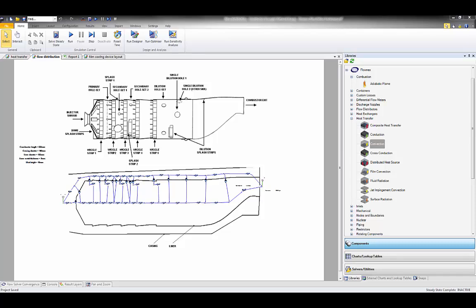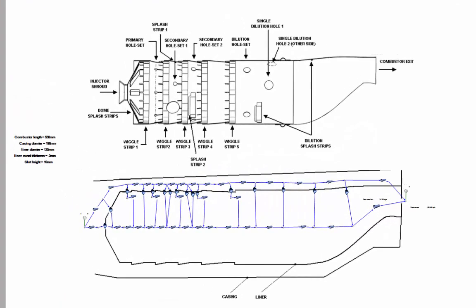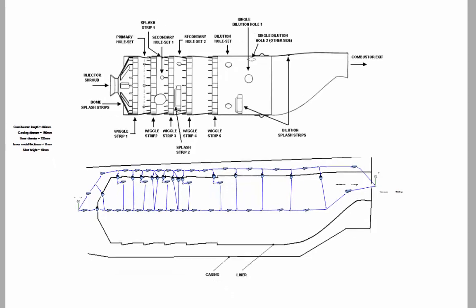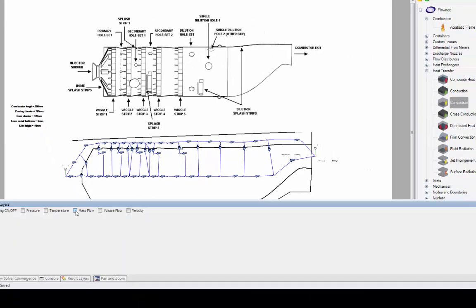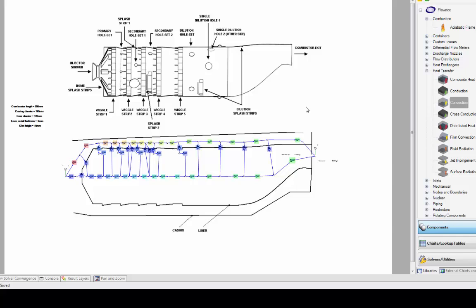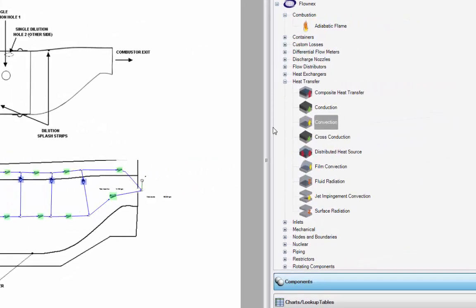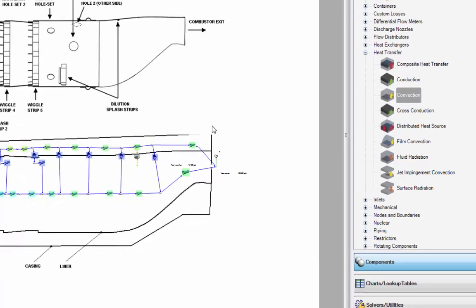What you can see is the flow distribution network laid out on the Flownex drawing canvas. Inputs to these flow components are pretty standard: cross-sectional flow areas, flow path length, various admission hole diameters, and discharge coefficients. This network gives a look at what the mass flow and pressure drop looks like through various sections of the liner. Once happy with those results, I can select components from the heat transfer library and integrate the heat transfer components with the cold flow model.